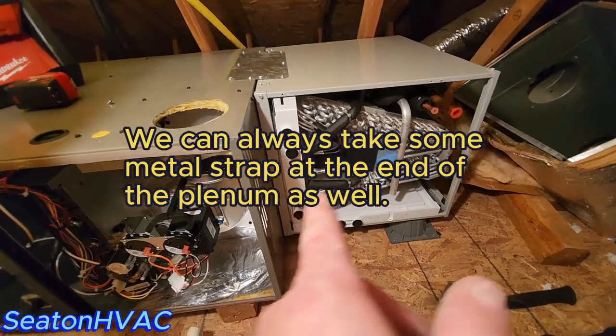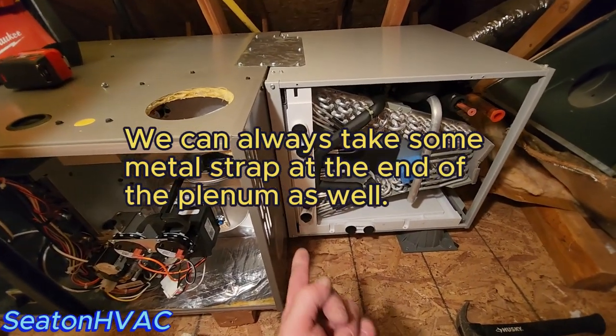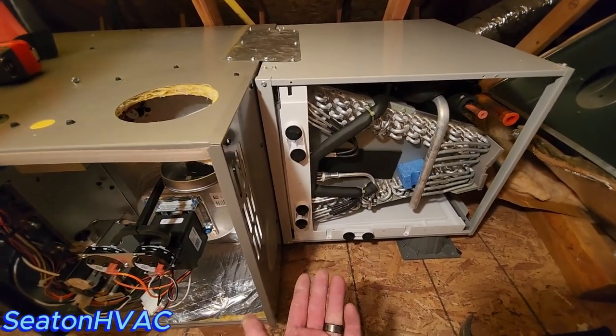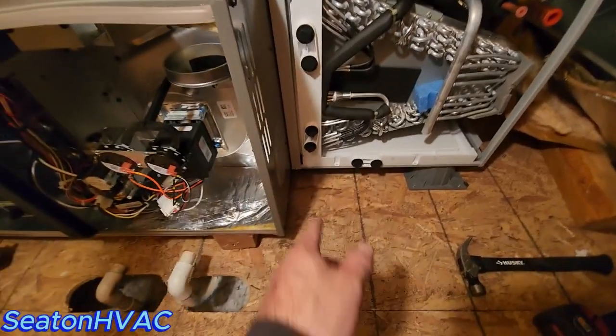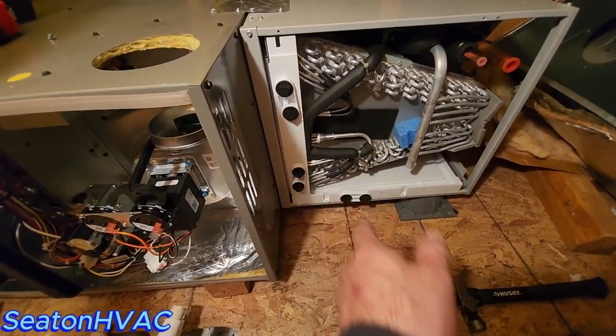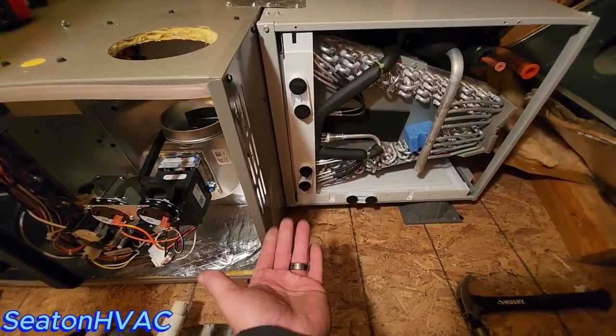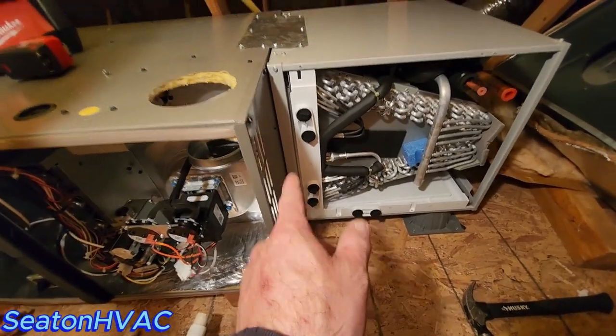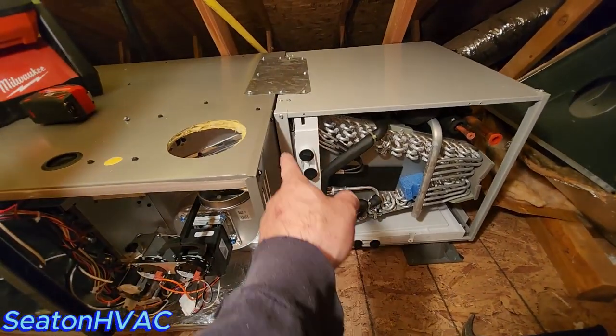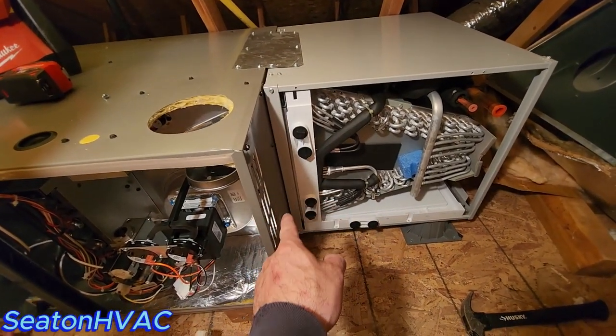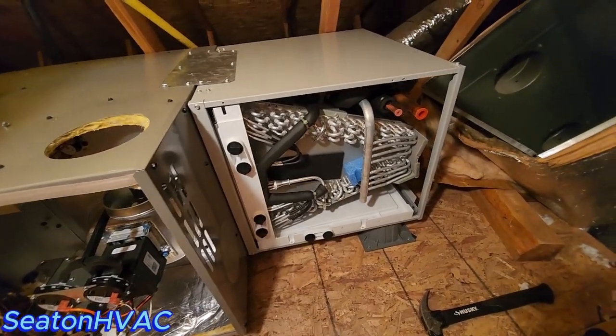What we're going to do is work together. We'll put a piece of mastic tape underneath on the bottom — that's what I'm always worried about when I can't pull the coil out, because it's tough to seal. We'll get a piece of tape under there, smooth it as good as we can, get our 3 sides, and then I'll probably just run a clean bead of silicone on the front side. No reason to tape that.